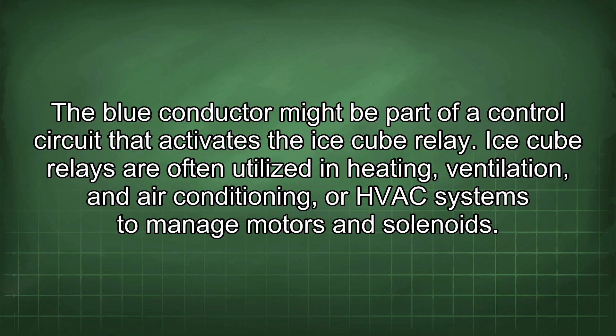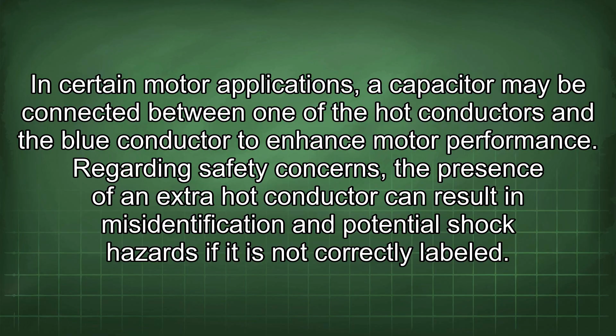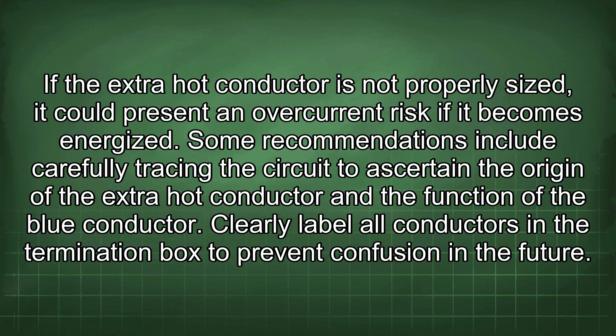Regarding safety concerns, the presence of an extra hot conductor can result in misidentification and potential shock hazards if it is not correctly labeled. If the extra hot conductor is not properly sized, it could present an overcurrent risk if it becomes energized. Some recommendations include carefully tracing the circuit to ascertain the origin of the extra hot conductor and the function of the blue conductor. Clearly label all conductors in the termination box to prevent confusion in the future. Ensure that all wiring adheres to current electrical codes to minimize safety hazards. If you're not comfortable working with electrical systems, seek advice from a qualified electrician for assistance.